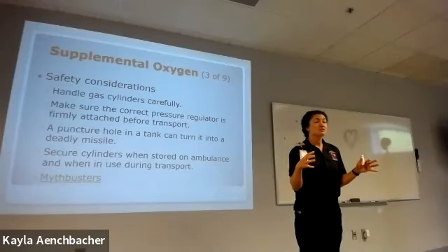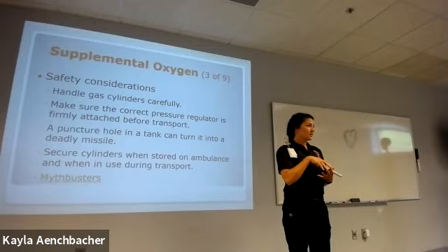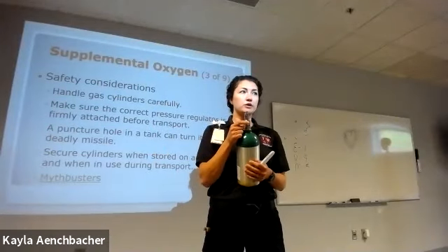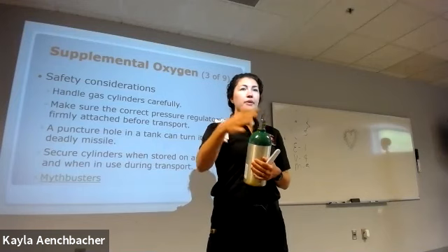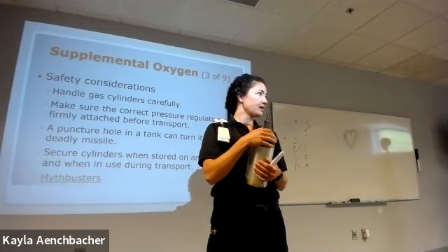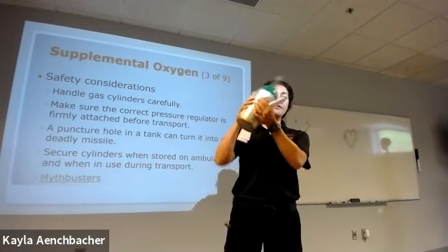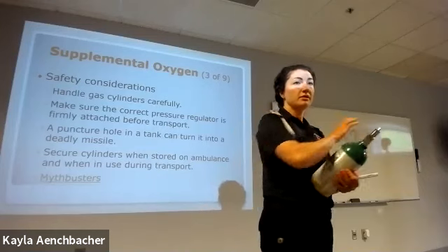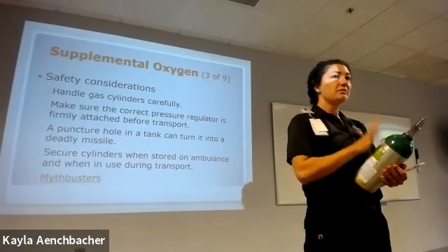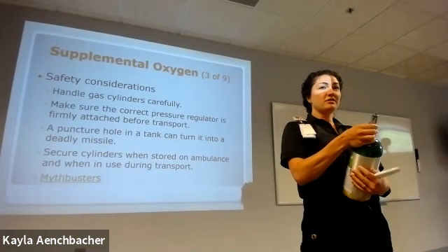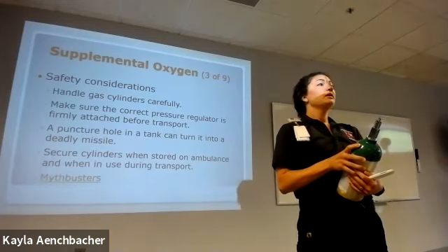All right, guys, if that oxygen tank is full, it's very pressurized on the inside. The way they work, you either assemble them yourself or they're pre-made, but there's a little neck right here where you connect what's called a regulator that allows a proper amount of pressure to flow in and out of this oxygen tank. If this is sitting straight up and it falls down, it's possible that the regulator becomes sheared off. That seal is broken, right? And what is this thing going to become if it has an open path for all of that pressurized oxygen? A torpedo. Literally a projectile.